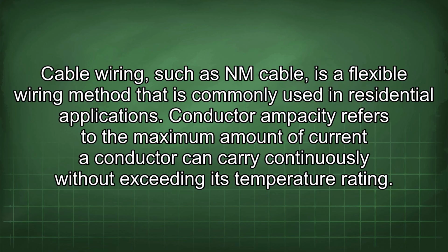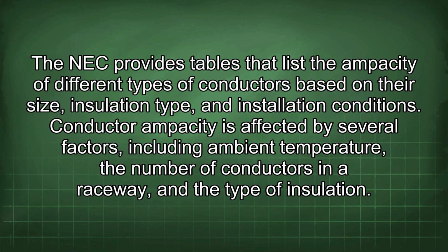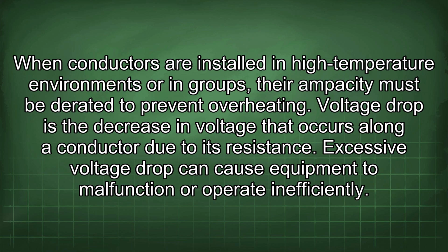Conductor ampacity refers to the maximum amount of current a conductor can carry continuously without exceeding its temperature rating. The NEC provides tables that list the ampacity of different types of conductors based on their size, insulation type, and installation conditions. Conductor ampacity is affected by several factors, including ambient temperature, the number of conductors in a raceway, and the type of insulation. When conductors are installed in high-temperature environments or in groups, their ampacity must be derated to prevent overheating.